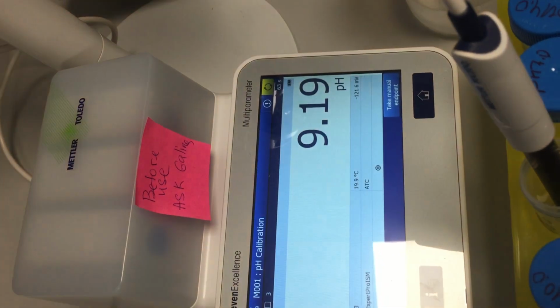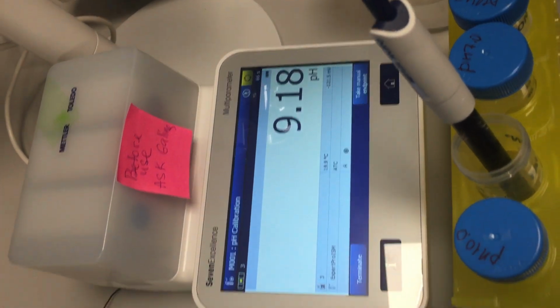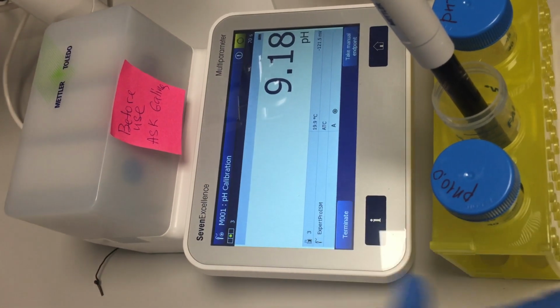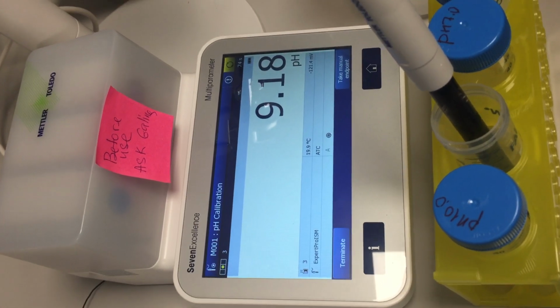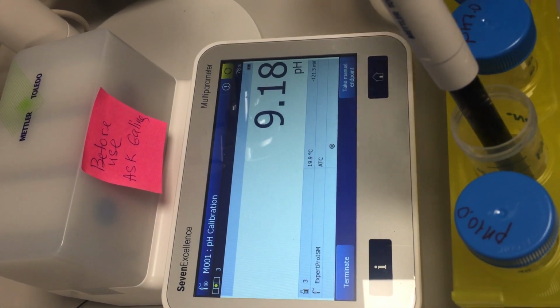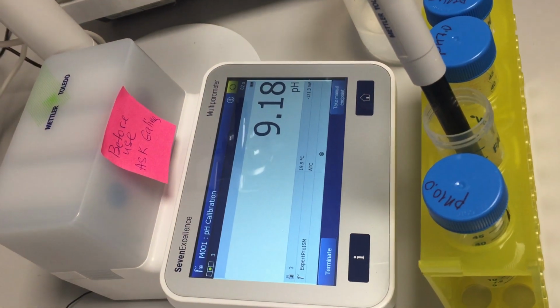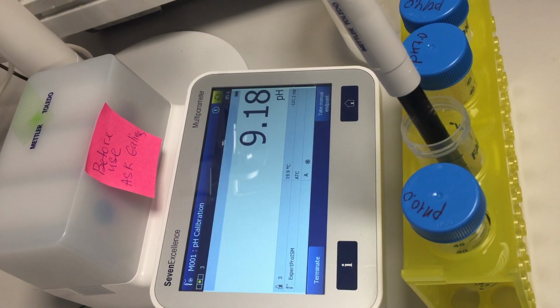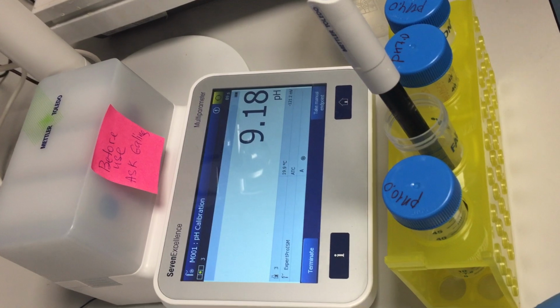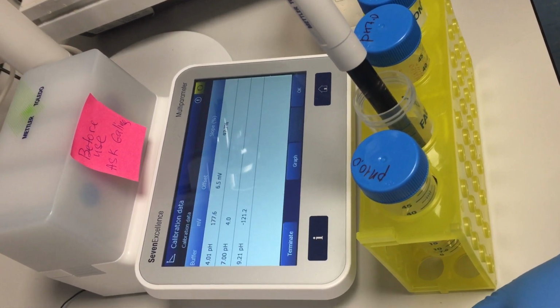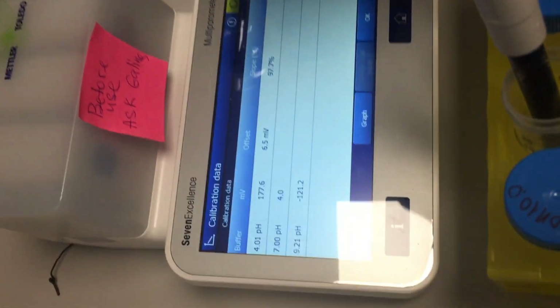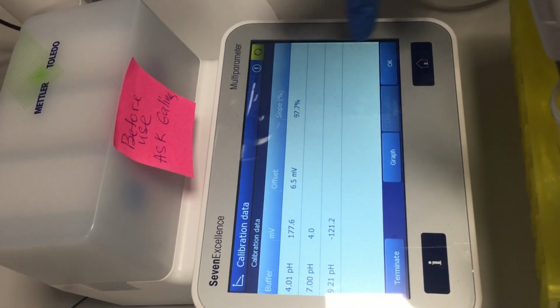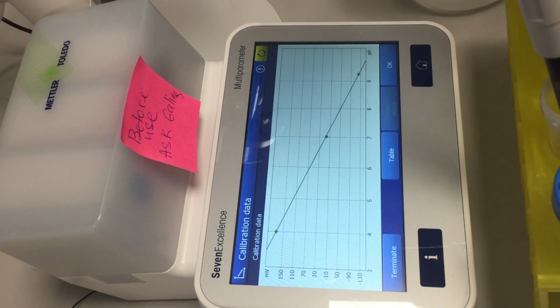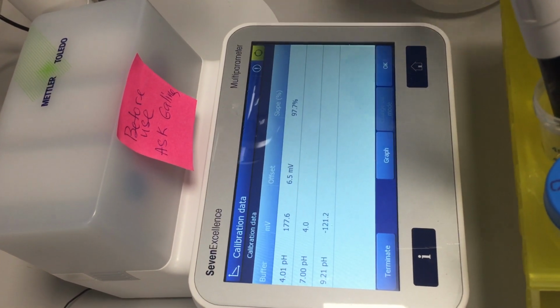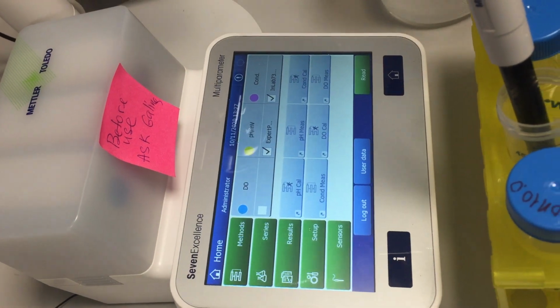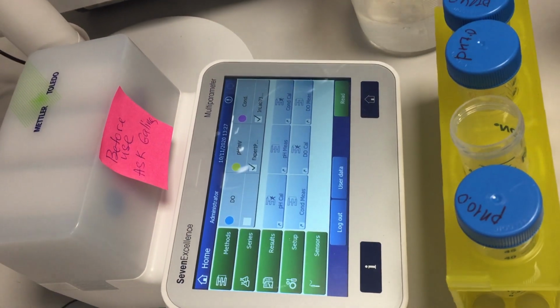The yellow one is still moving. And here it is showing how many points it took. Here and here. It also tells you the temperature. Yeah, it's also telling the temperature of the solution. So it has the temperature tip inside the pH, unlike the previous pH meter. And it's supposed to make your calibration curve whether the points are fitting. Yes, so this is the calibration data, and it is showing the slope 97.7. So you can show the graph, you can show the table, whatever you like, and pressing OK. So then it's made all the calibration, so you have your calibration results.